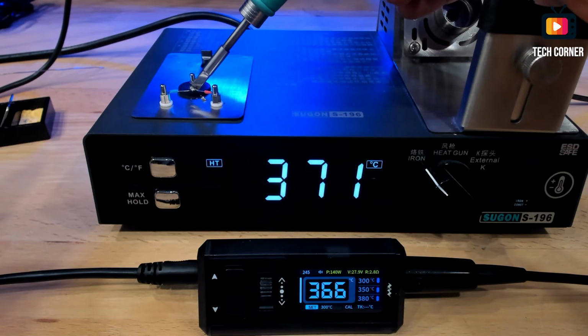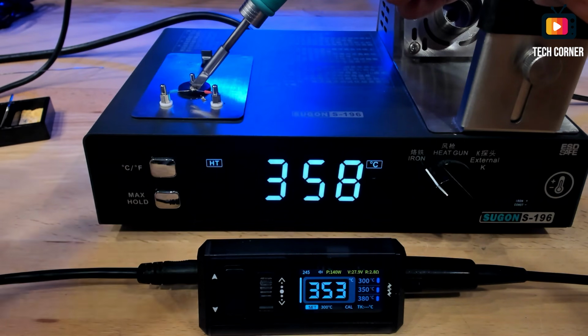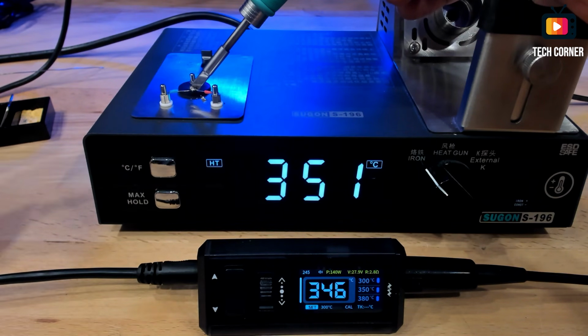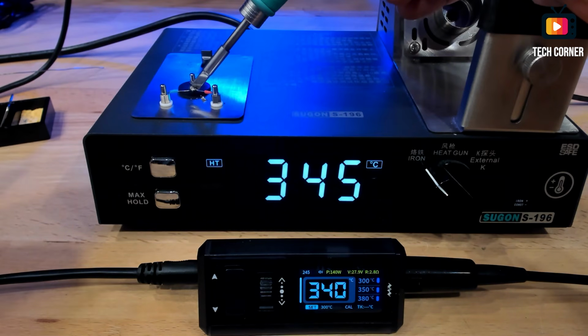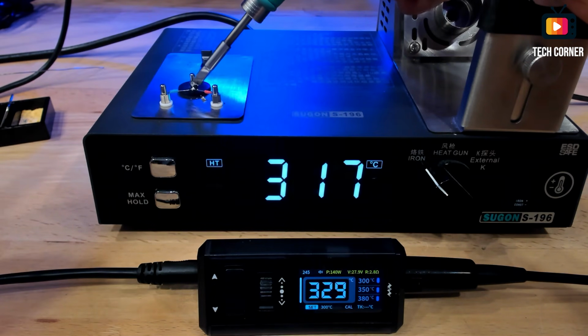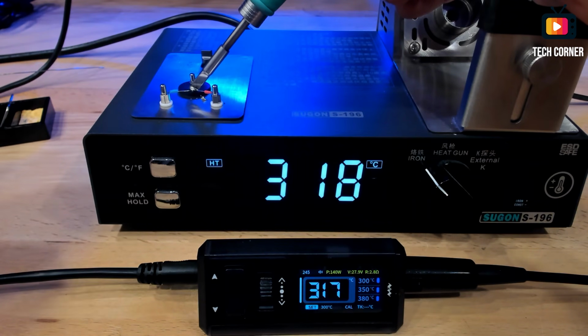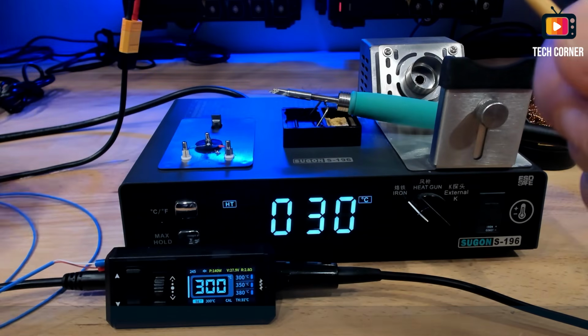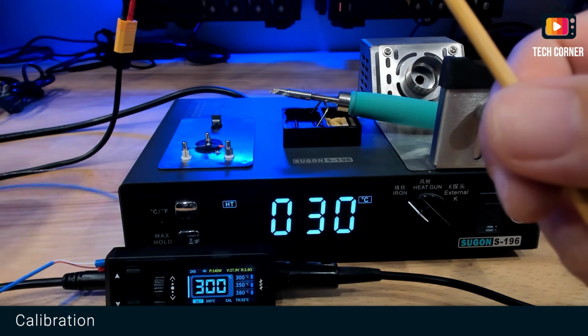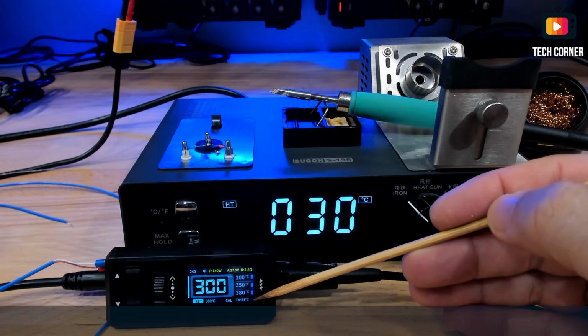Normally you will have some difference on the lower range of the temperature, but this one is, from the minimum, 100 degrees, to the maximum, always spot on. Very nice indeed. Okay, so this for me is a winner, total pass, amazing. Let's see the calibration process, and as you know, here in the bottom you have the temperature of this probe.